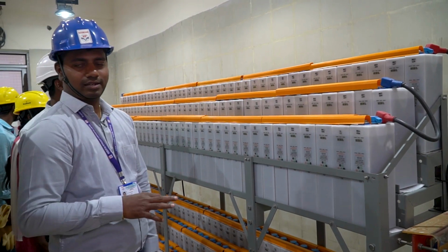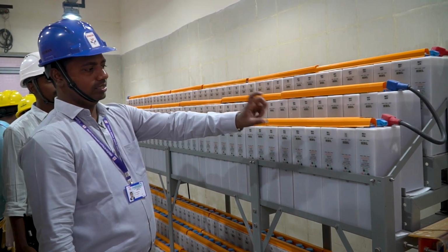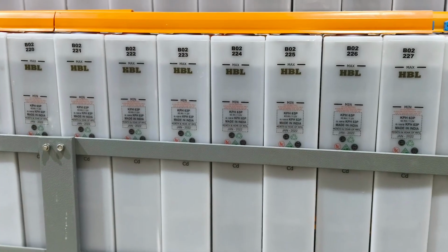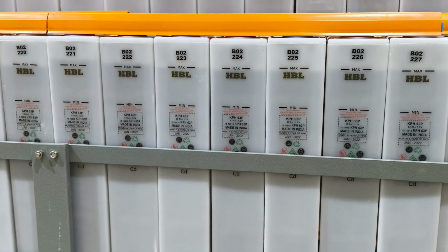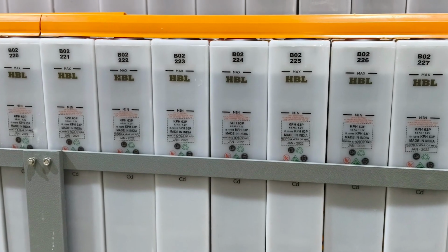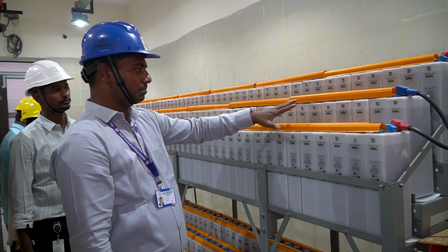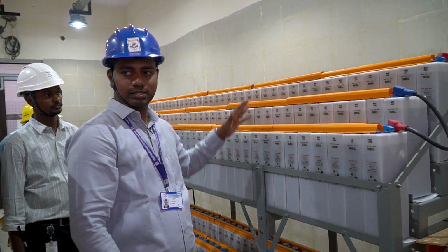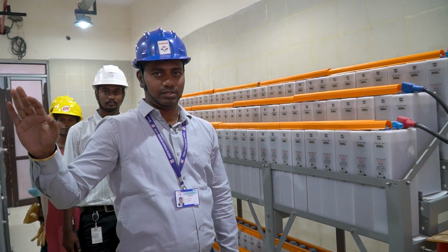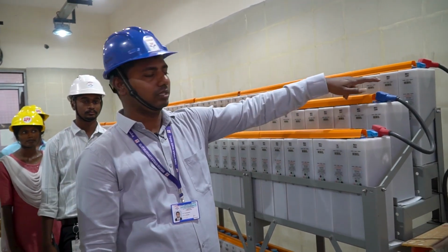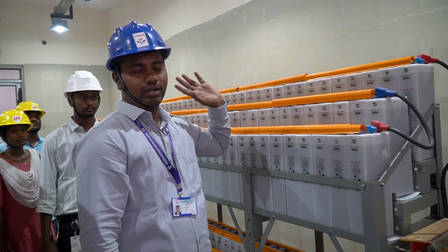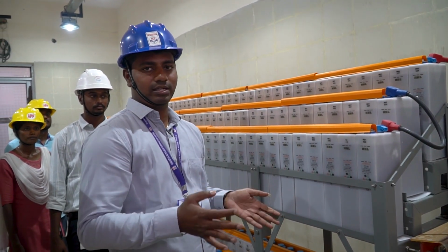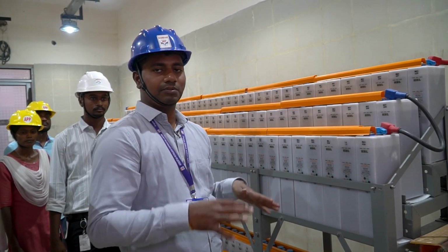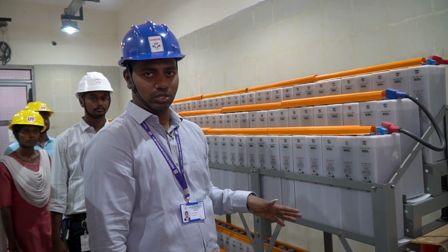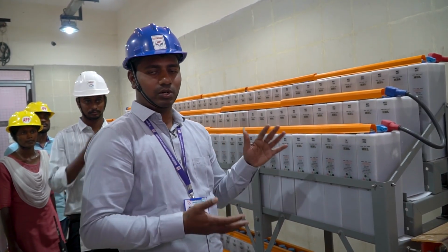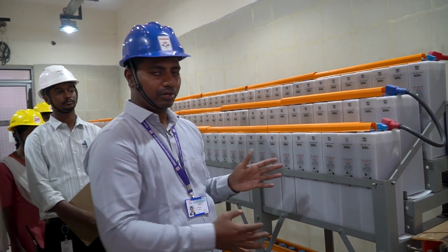So presently we are in a battery room. All these individual battery cells of 1.2 volts have been connected in series to cater to the 40 kVA UPS. This battery set covers one 40 kVA UPS and this set will cover the other 40 kVA UPS. There are approximately 328 battery cells, and they will cover the entire instrumentation critical power supply. If regular power supply is not there, this will automatically switch on, and the minimum power backup required by the instrumentation will be provided by these batteries.